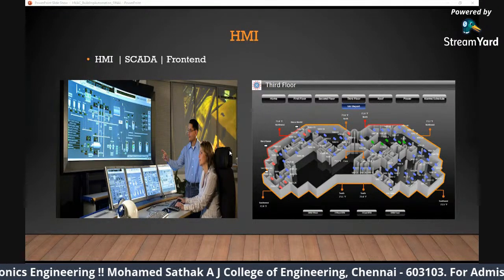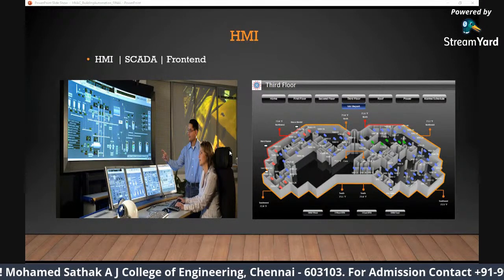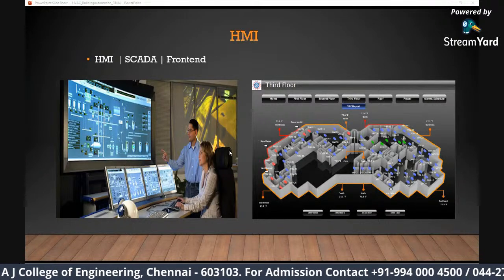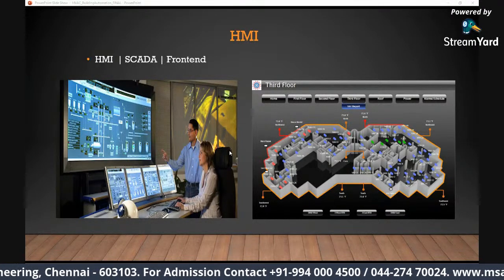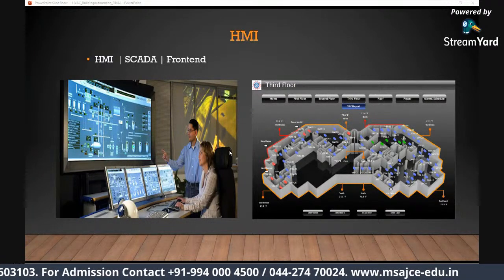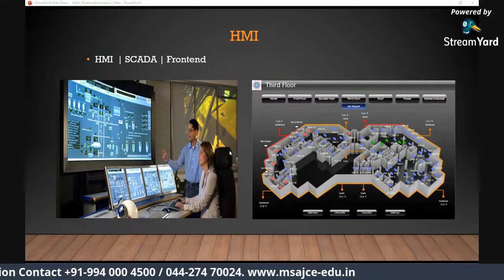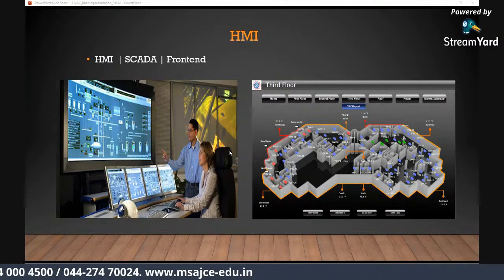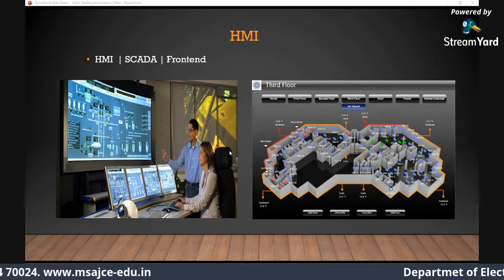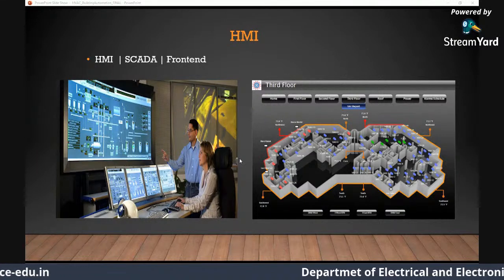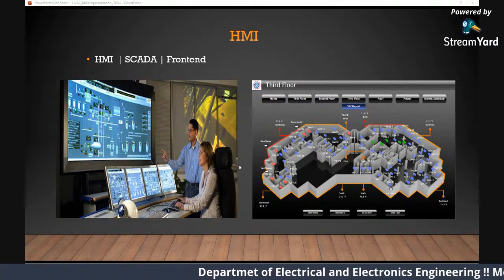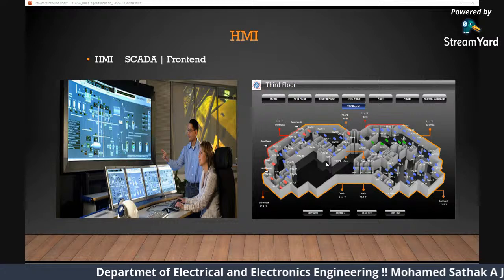So your front end is your user interface between the operator and engineer, where they can monitor the complete operation of a building. They can shut down the building in one click. They can turn on the building in one click. Okay. So your front end is your complete user interface between your operator and the building. We have to design all the graphics, show every point in the building.